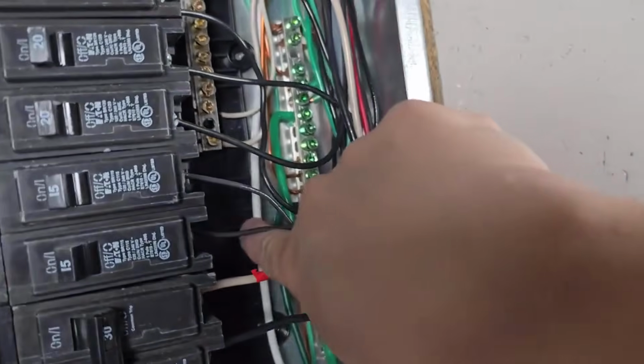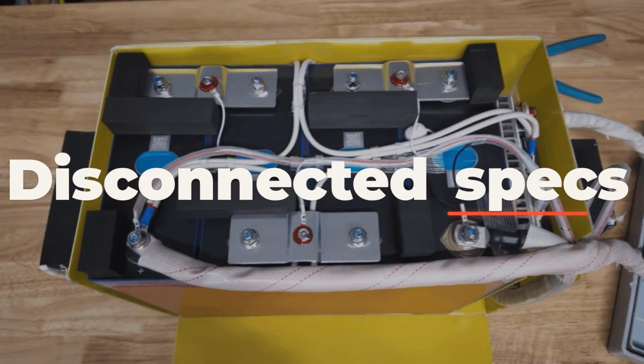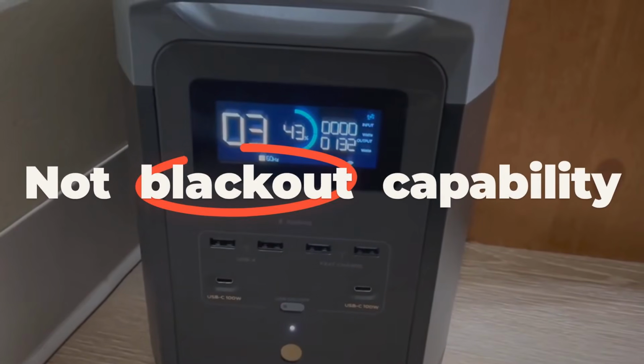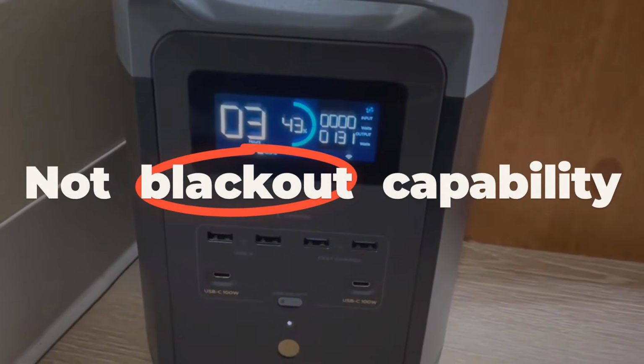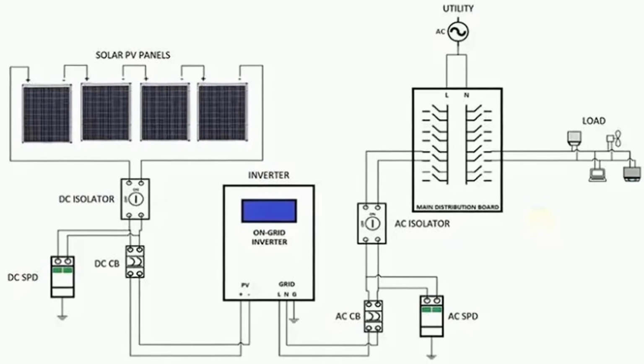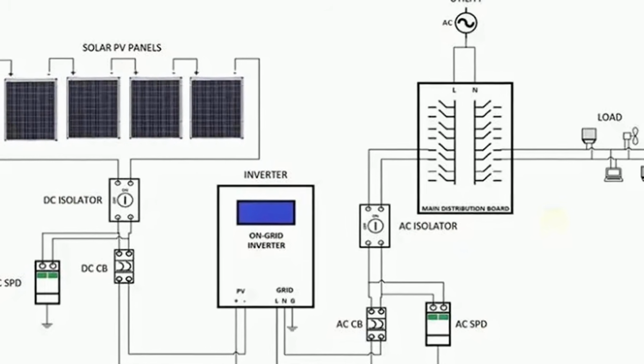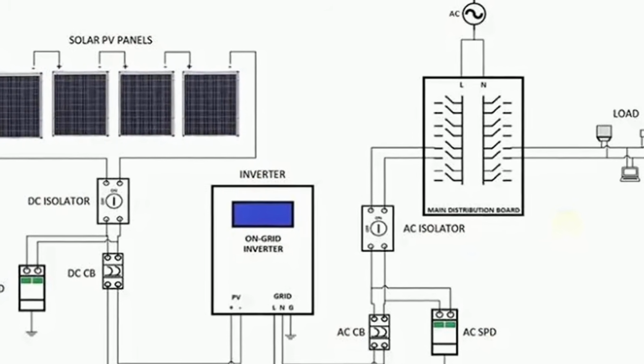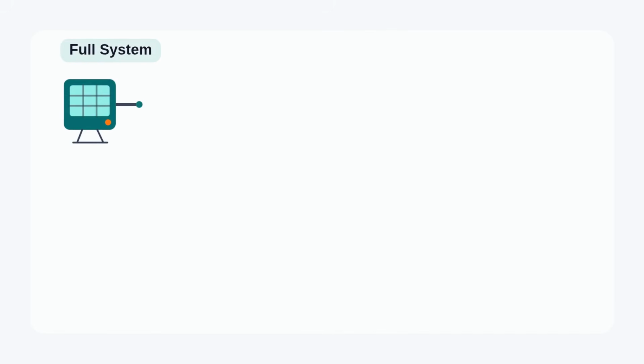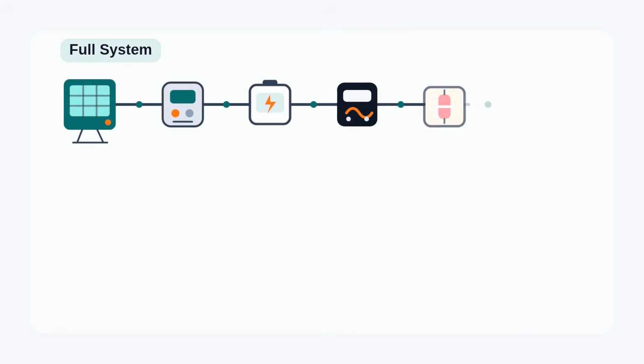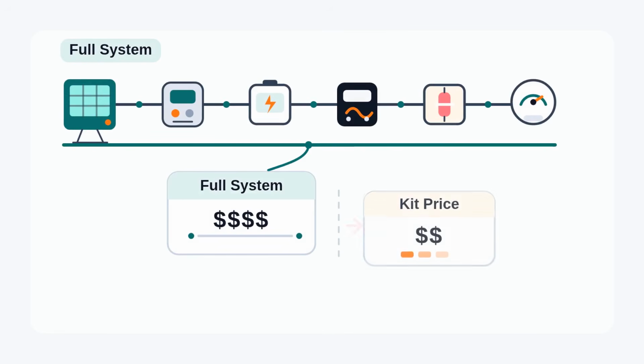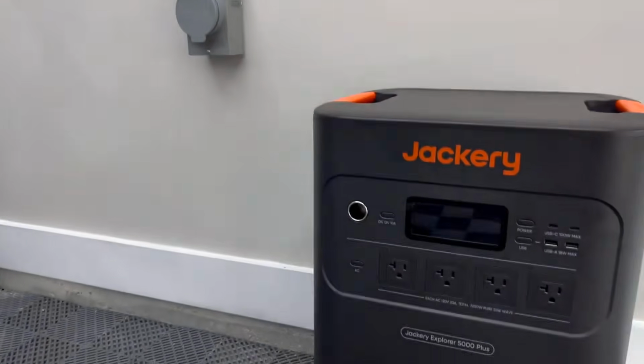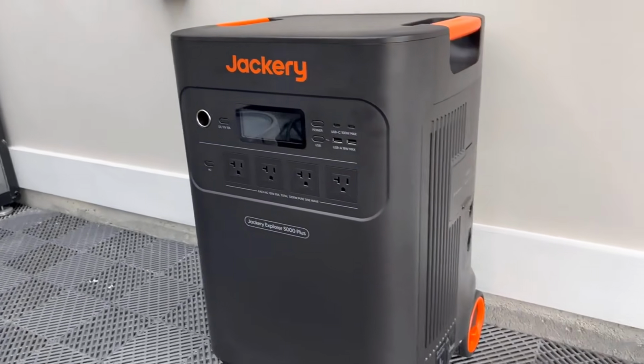That is not an argument that cheap kits are fraud. The narrower verdict is this. Disconnected specs were bundled and sold as if their combination equaled blackout capability. It does not. Each component was rated independently under ideal conditions that do not overlap in the real system. The buyer inspection is one rule. Price the complete engineered chain, then compare that number to the kit price. If the gap requires parts that are essential to the job, the advertised price was never the backup price. It was the price of the box.